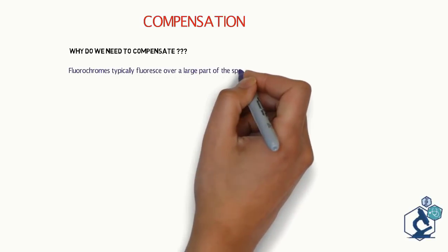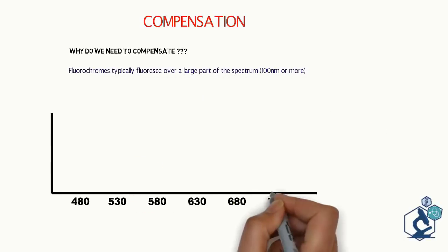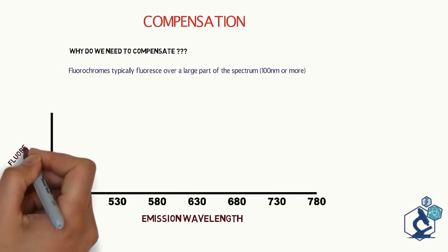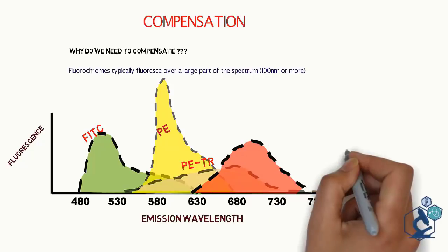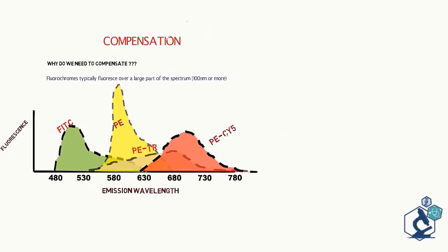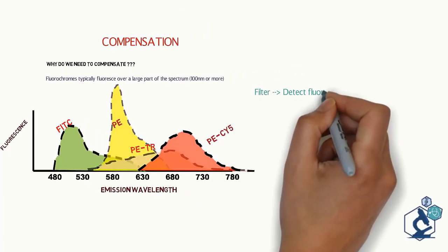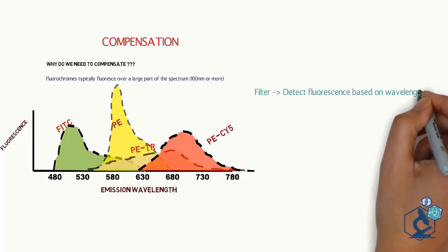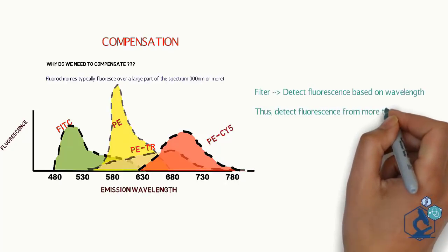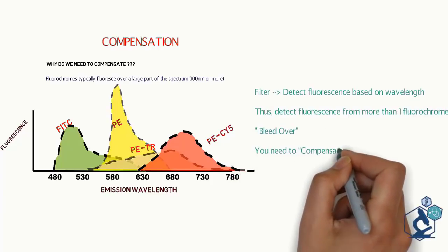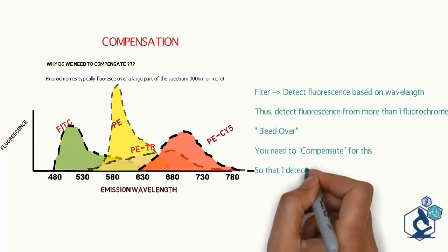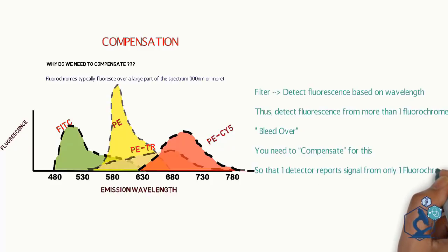Compensation. Fluorochromes typically fluoresce over a large part of spectrum, 100 nm or more. This graph shows emission wavelength of few commonly used fluorochromes. As we can see that there is an overlap among these emission wavelengths. Depending on filter arrangement, a detector which detects light on the basis of wavelength may hence detect some fluorescence from more than one fluorochromes, which is referred to as bleed over. We need to compensate for this bleed over so that one detector reports signal from only one fluorochrome.